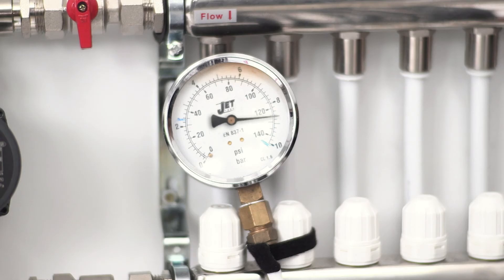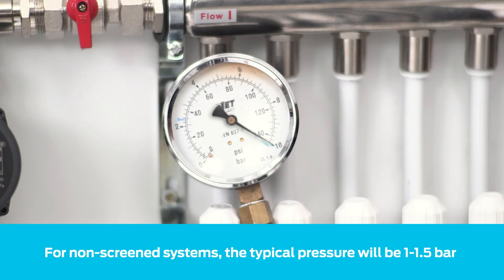If all is well, increase the pressure to 10 bar and leave for a further 10 minutes while checking for leaks or pressure drops. If all is well, reduce pressure to the operating pressure.